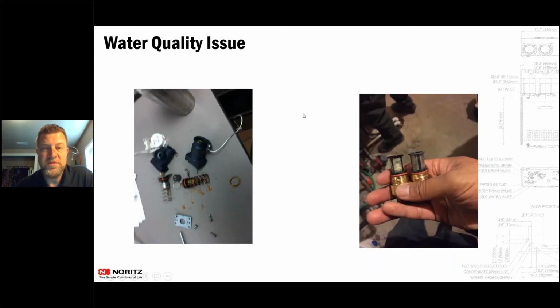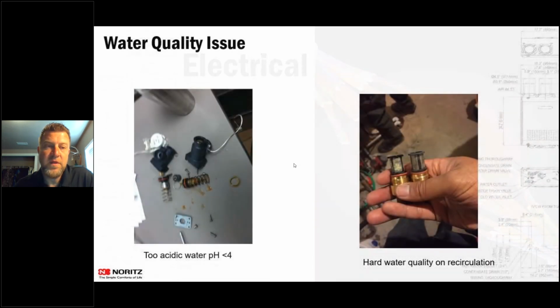So some water quality issues that you'll see: if somebody has too acidic water, a pH level lower than 4. So this was like deionized water at an ice rink, and that actually ate away a lot of that valve. Having hard water and going through a recirc system will gum up the inlet filters. Every single one of our units has a little screen on the inlet going into the unit. It blocks any foreign debris from going through the unit, but it will scale up over time.